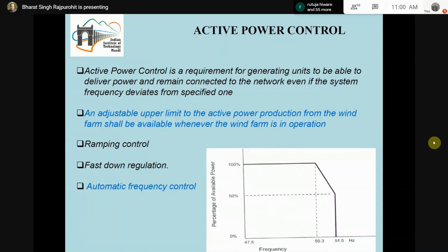But what is the advantage? The advantage is that as soon as frequency regulation is required, we will be able to increase from 90 to 100. So this means there is a continuous wastage of energy, but the capability is also there to participate in the frequency control. So this is what you are able to see in this curve.